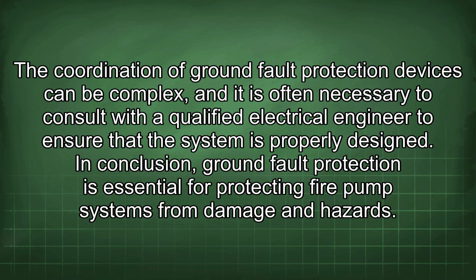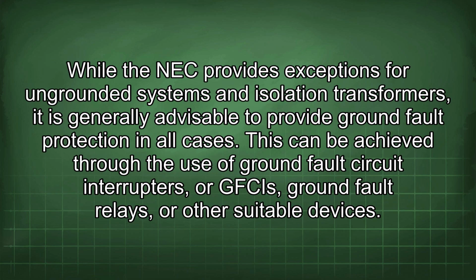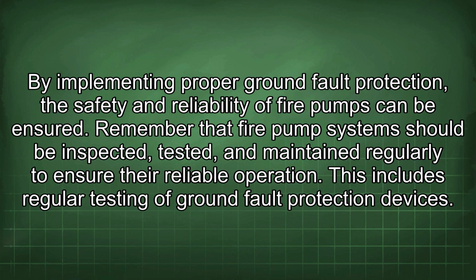In conclusion, ground fault protection is essential for protecting fire pump systems from damage and hazards. While the NEC provides exceptions for ungrounded systems and isolation transformers, it is generally advisable to provide ground fault protection in all cases. This can be achieved through the use of ground fault circuit interrupters, or GFCIs, ground fault relays, or other suitable devices. By implementing proper ground fault protection, the safety and reliability of fire pumps can be ensured.